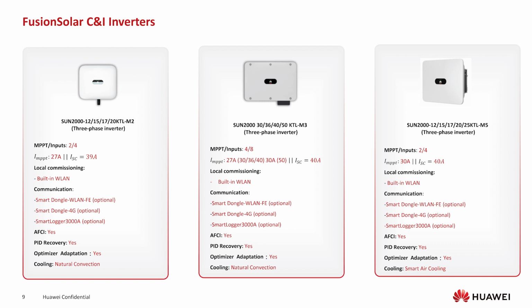Then we also have another version here, which is the newer Sun 2000, 12, 15, 17, 20, 25 kilowatt M5 version. It's similar to the other one. The difference is you've got 30 amps rated current, and the short circuit current is 40 amps. It's got built-in WLAN, and all the rest: AFCI, optimizer ready, smart air cooling. This has smart air cooling, so this one has fans in there.